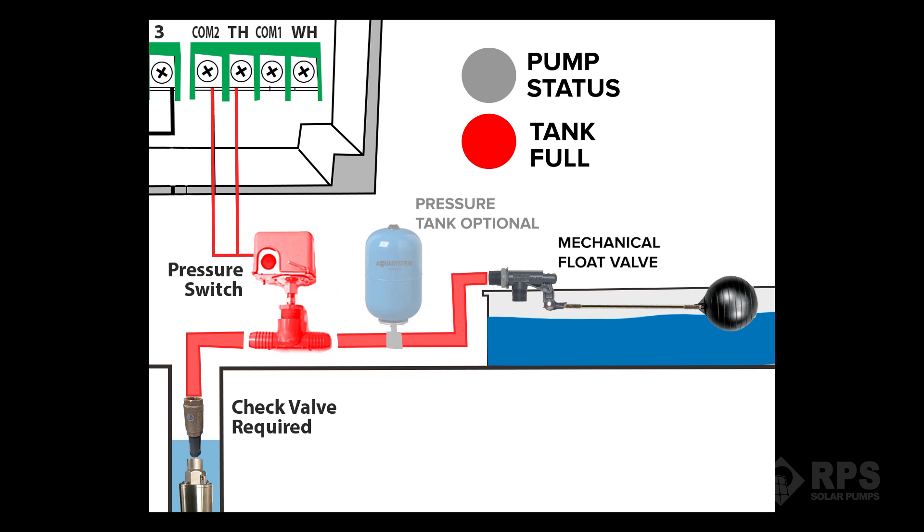Okay so we have the reverse situation here where your cows are slowly drinking down the water, the trough is emptying and opening the valve. This will release the pressure in the line and cause the contacts to open in the pressure switch. This will tell the controller that the tank is no longer full, the pump status begins to illuminate and water begins to flow through the system.